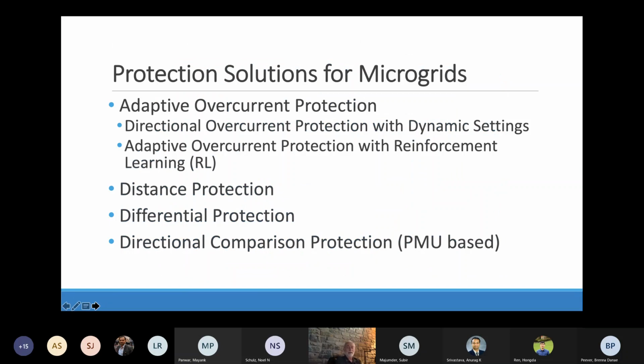Adaptive overcurrent protection is still doable, but it could be and should be coupled, for mostly radial networks, with directional overcurrent protection having dynamic settings for the reasons we mentioned. Settings can no longer remain the same when you have multiple generators and rapidly changing load levels in the system that did not exist before when traditional overcurrent protection relays were designed. It could also be done using more advanced approaches like reinforcement learning or any types of machine learning.